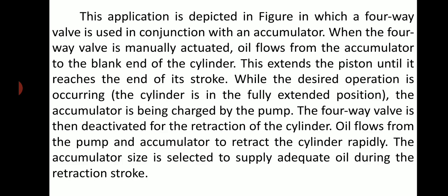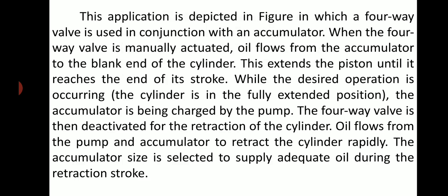While the desired operation is occurring, the cylinder is in the fully extended position. The accumulator is being charged by the pump. The four-way valve is then deactivated for the retraction of the cylinder. Oil flows from the pump and accumulator to retract the cylinder rapidly. The accumulator size is selected to supply adequate oil during the retraction stroke.